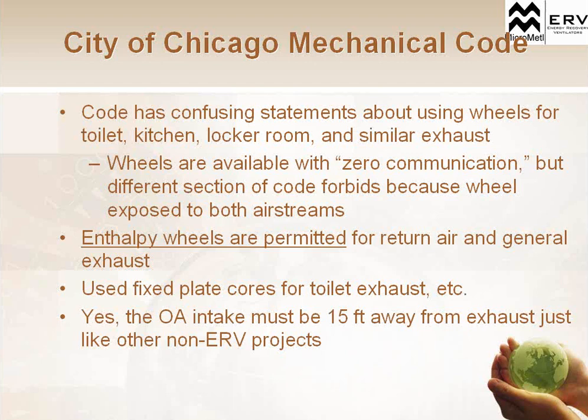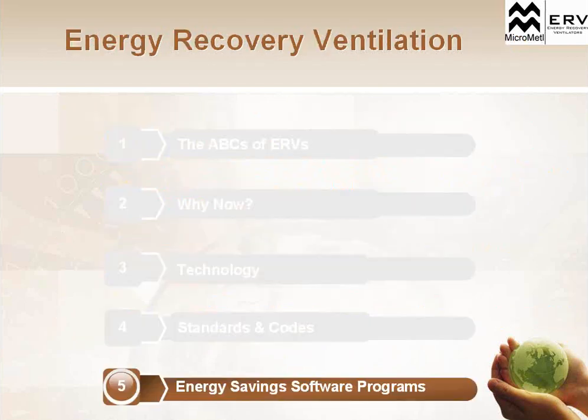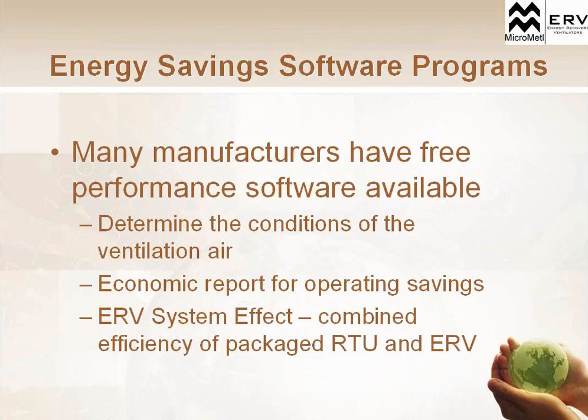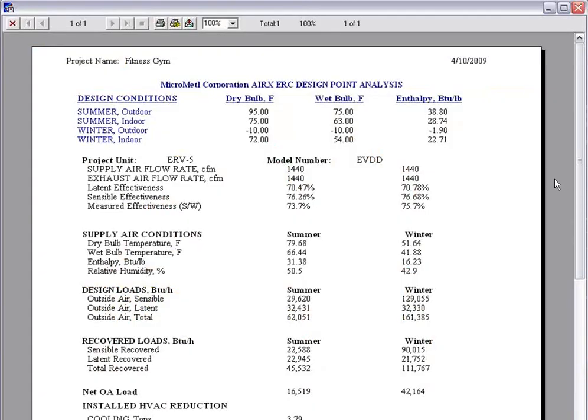But predominantly in the commercial marketplace, you're using a wheel application, which is the topic of our discussion today. So if we look at some of the energy-saving software programs, a lot of manufacturers have free performance software for energy recovery units themselves. For the air exchange wheels themselves, they provide software. This is the air exchange software where we would actually type in the amount of CFM that we're supplying and exhausting, whether it be balanced or unbalanced. We'll give our outdoor air conditions, our return air conditions of the system, and we would select a specific wheel model, and it would give us what we would get on our entering air temperature conditions.